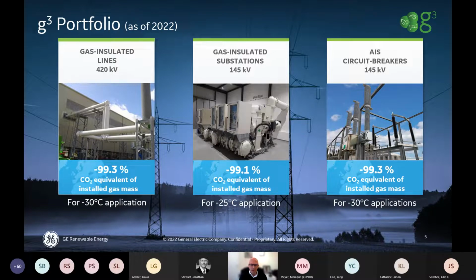So only using that gas mixture that we call G-cube, G to the power of 3, for gas insulated line. So we can take an existing insulated phase bus duct, and that's actually the one you see in a critical substation, 420 kV in UK, where we replace some of the existing SF6-filled gas lines with G-cube ones, for a dramatic overall CO2 equivalent reduction.